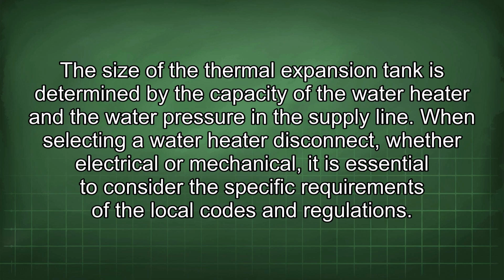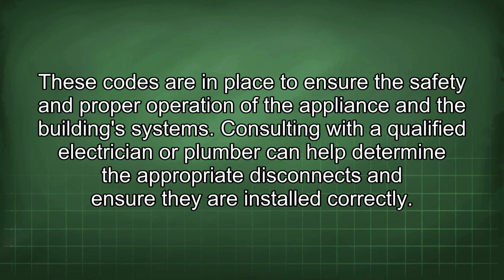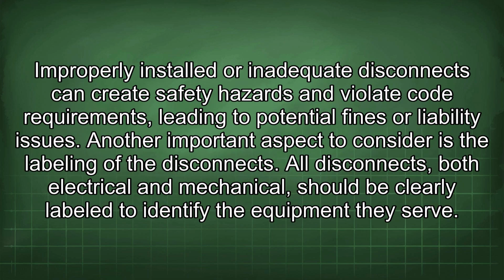in the supply line. When selecting a water heater disconnect, whether electrical or mechanical, it is essential to consider the specific requirements of the local codes and regulations. These codes are in place to ensure the safety and proper operation of the appliance and the building's systems. Consulting with a qualified electrician or plumber can help determine the appropriate disconnects and ensure they are installed correctly. Improperly installed or inadequate disconnects can create safety hazards and violate code requirements, leading to potential fines or liability issues. Another important aspect to consider is the labeling of the disconnects. All disconnects, both electrical and mechanical, should be clearly labeled to identify the equipment they serve.